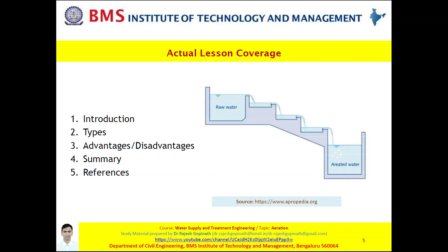Slide 6. So what is basically aeration? It's a simple process wherein air is brought in contact with water or water is brought in contact with air. Thereby, you facilitate an air-water interface which allows exchange of gases. Now, the rate at which the exchange of gases will take place would depend on several factors, such as the area available for exchange, also the rate of absorption and desorption with respect to specific gases, with respect to their partial pressures. It also depends on when an equilibrium is reached. It also would depend on temperature.